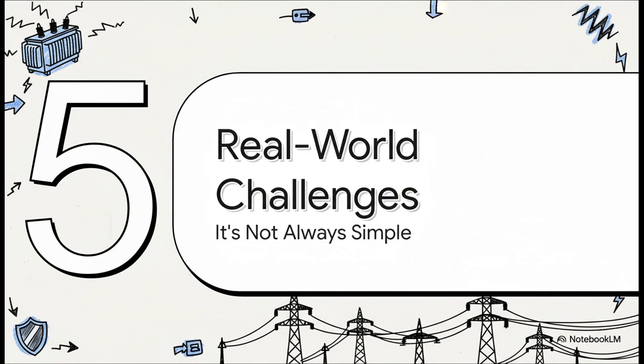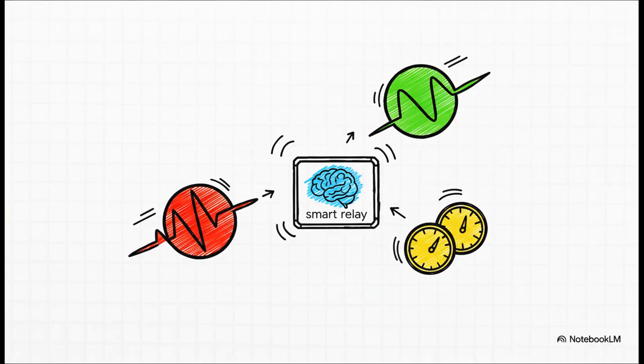Because trying to apply this beautiful, elegant theory in the real, messy world, well, that comes with some major headaches that engineers have to solve. See, the protection system has to be smart enough to tell the difference between a real fault and a few common curveballs. For instance, the sensors that measure the current aren't always perfect. The transformer's own wiring can actually shift the timing of the electricity just a little bit. And the big one, just turning a transformer on causes this huge but totally normal spike of current called inrush that looks almost identical to a catastrophic fault.